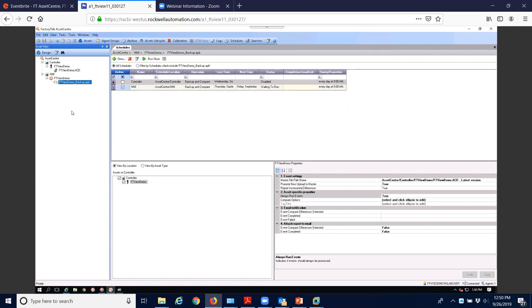The other part I would argue with, and I know where you're coming from on that one: because it's a process system, there are times where there's no need to upgrade. There's no reason to go from a 3.6 library to a 4.0 library just because. Most of the time it's on the feature set side. Patching is usually on the security side or elsewhere, and the way the screens look is usually outside of that scope. But if the argument is that we need to do all of this, as long as you can update both of them from the server side and probably test it offline first, you can do all of that while you're online. As long as the controller is redundant, that is usually how it works if you needed to do firmware upgrades and things like that. If it's just the AOIs, you can do it all online and you don't run into any issues.